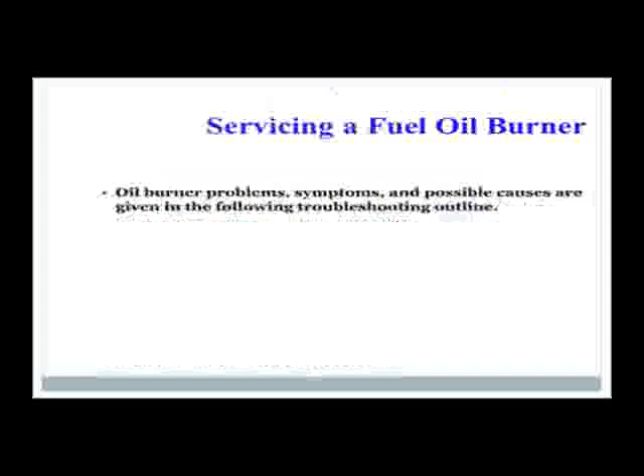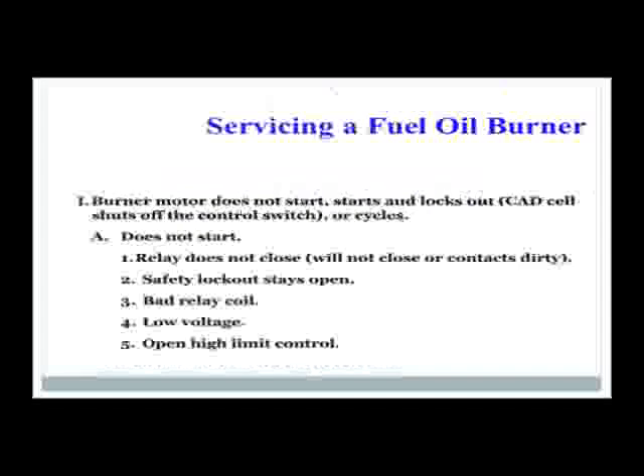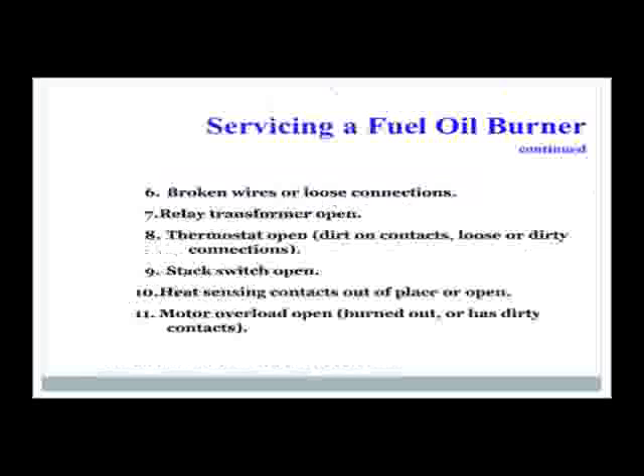Oil burner problems, symptoms, and possible causes are given in a troubleshooting outline. First, burner motor does not start and locks out or cycles. Okay, A: does not start. Possible relay not closing, safety lockout open, bad relay coil, low voltage, or an open high limit control. You might also have broken wires. You might have a transformer open. You might have a thermostat open. Stack switch or heating contacts out of place or open. Might be a bad motor overload.